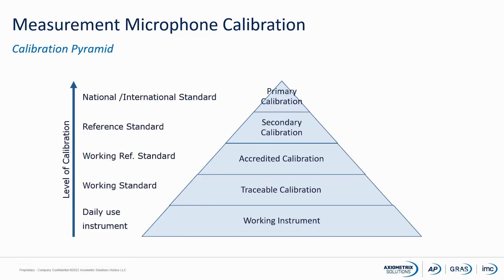If we look at the calibration pyramid, then at the bottom of the pyramid we have the daily use instruments. It's actually all the microphones or the analyzer, whatever you are using. Most of you are using them daily for doing measurements. These are the working instruments. These instruments will, from time to time, maybe once a year, depending on your quality system, be sent in for calibration.